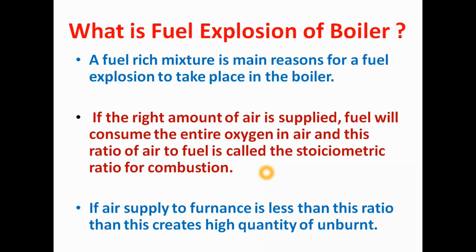After some time, the unburned fuel accumulates too much, and finally if we supply more oxygen to that unburned fuel, it will start to burn in an explosive manner. This is how the fuel explosion takes place in a boiler — due to accumulation of unburned fuel in the furnace caused by low supply of oxygen or air for combustion. This is the main reason.